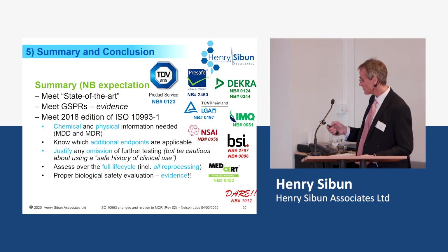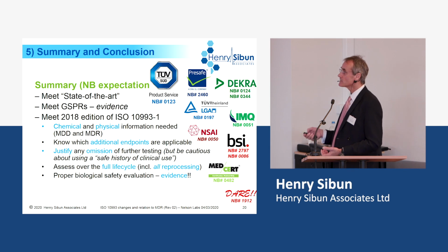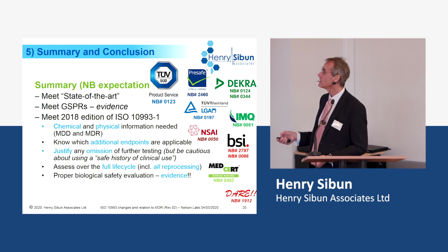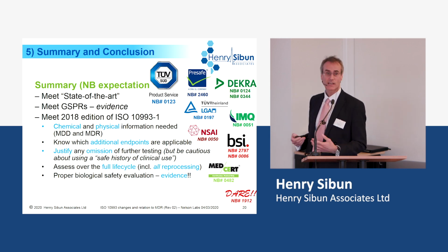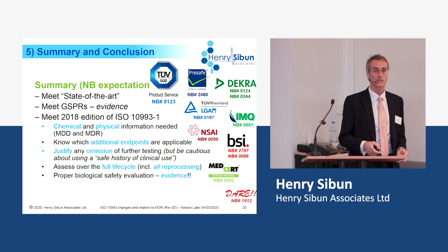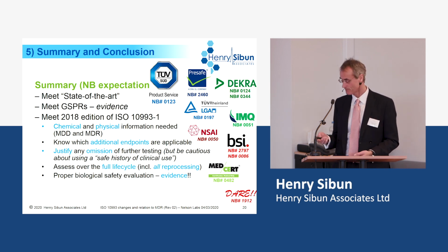And basically this means that you have to cover your chemical and physical information. Make sure you've documented it. Additional endpoints have been considered. You've justified why you haven't done testing if you've not done additional testing. You've covered the full life cycle. And the most important thing is please just have some evidence. If you submit just a pile of test reports, that will not be acceptable. You need to review those and to judge what it means from a risk point of view.